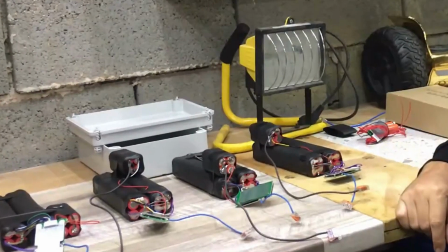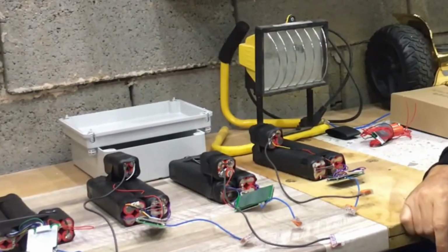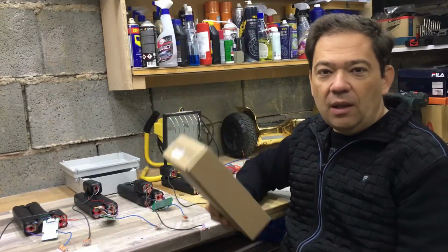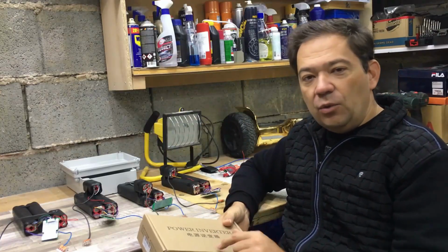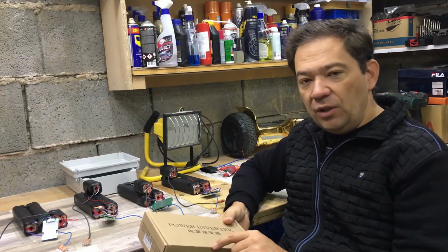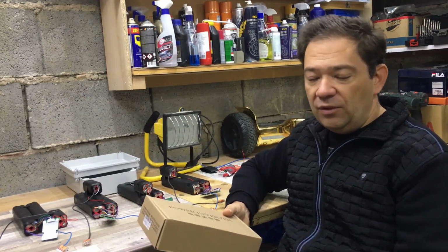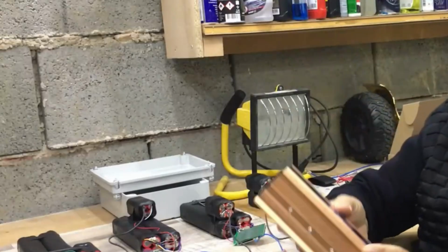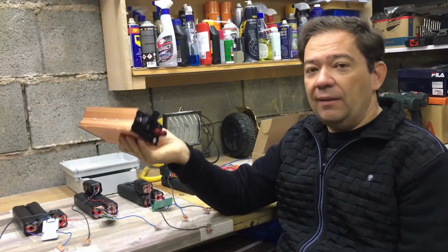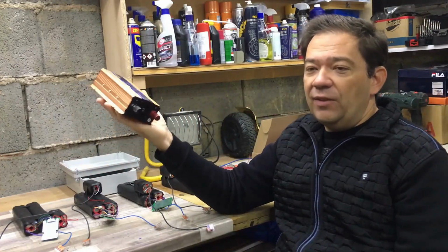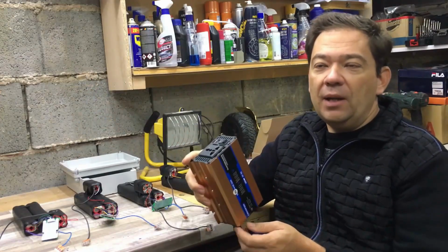In the next part, I'll show you a very short test of this device here in my hand, in the box. It's an inverter, a 48-volt inverter, so it converts 48 volts into 220 or 240 volts. It was sold as a 2,000-watt inverter, but in reality it can handle about 500 watts. The manufacturer claimed 2,000 watts, which it can barely survive.